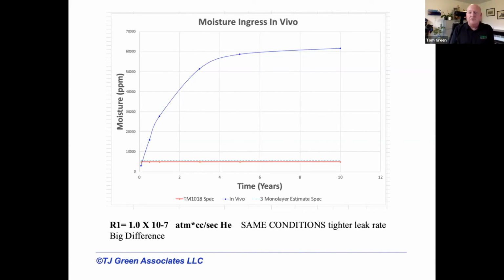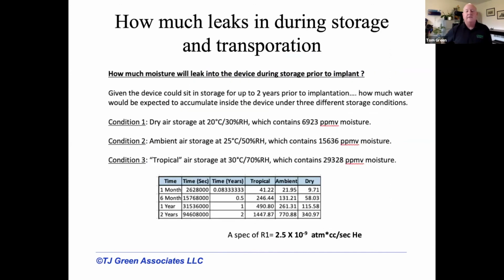So these kind of projections are important in development, to first of all establish what is my baseline RGA number I can expect right after seal, and then what is my leak rate, in order to say you want a device to last 5 years or 10 years in vivo. Now, the other thing you got to concern yourself with is, sure, in the body, you never move off of 37 degrees Celsius, so you got other problems.